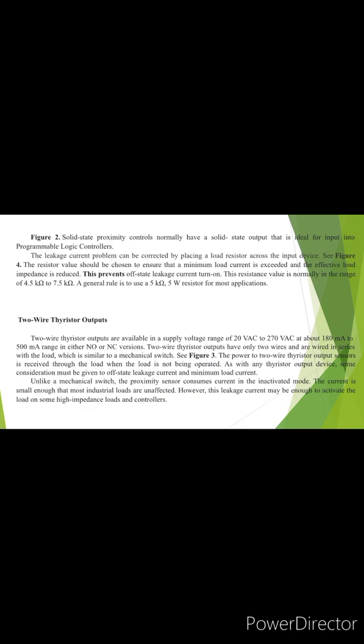Two-wire thyristor outputs. Two-wire thyristor outputs are available in a supply voltage range of 20 volts alternating current to 270 volts alternating current at about 180 milliamperes to 500 milliamperes range in either NO or NC versions. Two-wire thyristor outputs have only two wires and are wired in series with the load, which is similar to a mechanical switch. See Figure 3. The power for two-wire thyristor output sensors is received through the load when the load is not being operated. As with any thyristor output device, some consideration must be given to off-state leakage current and minimum load current.